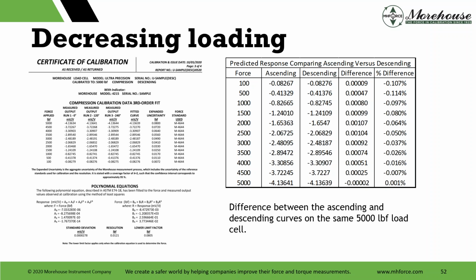Descending load, here we go. Predicted response comparing ascending versus descending. If you look at this, here's the same load cell. And this customer had us calibrate this load cell ascending and descending. If we look at the difference on the force point at 100 pounds, the ascending curve gives us 0.08267. Descending curve gives us 0.0827. Difference of 9 counts. And that is a percentage difference of 0.107. Here at 500, 0.114. And if you look at capacity, there's really no difference.